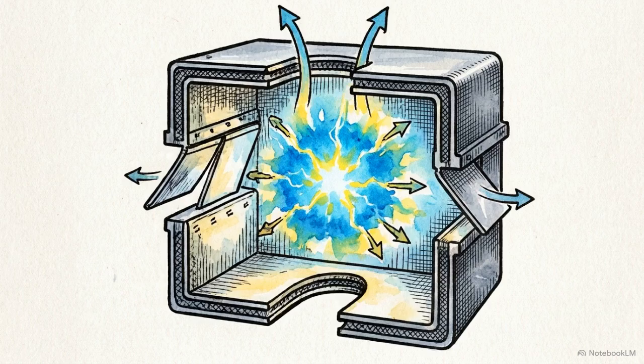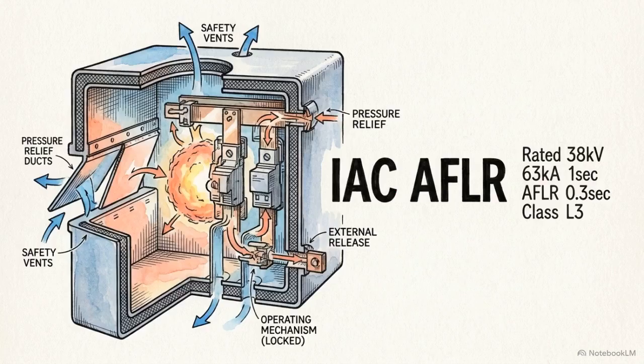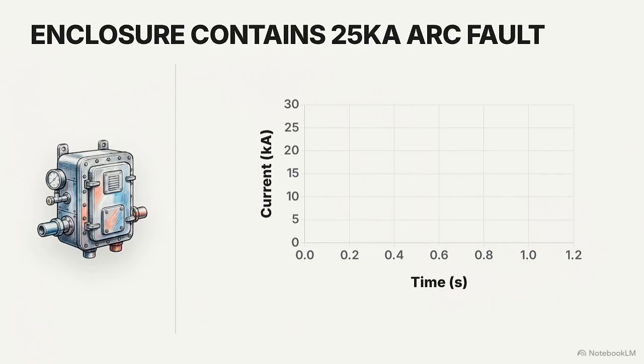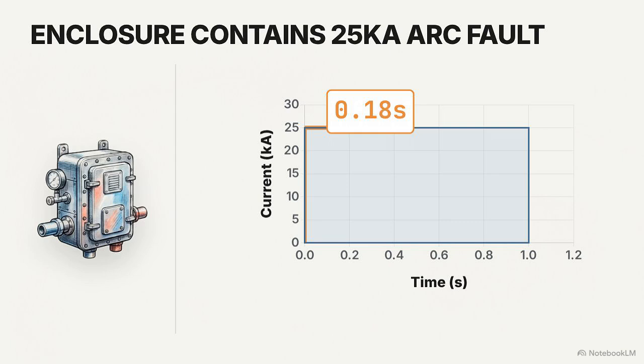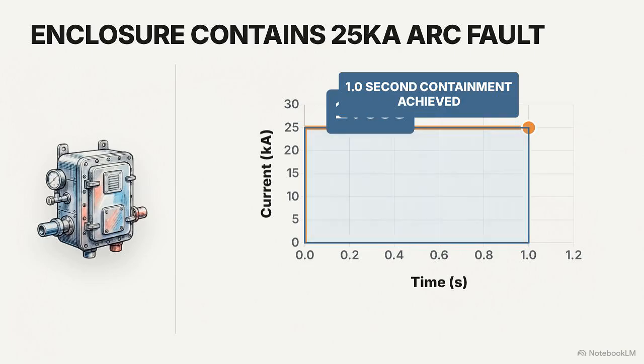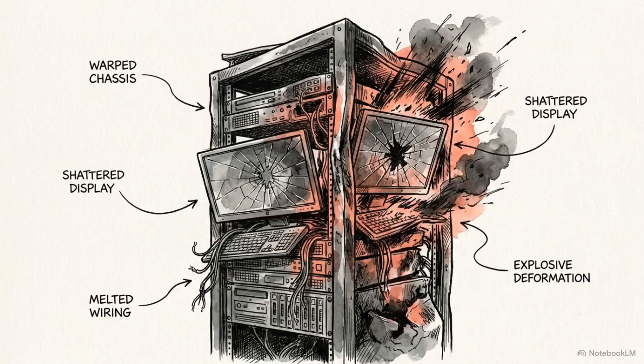If a component fails inside this sealed unit, the resulting arc flash generates immense pressure and heat. Therefore, the enclosure is built to meet a specific protection parameter, the Internal Arc Classification, or IAC-AFLR standard. A rating of 25 kiloamps for 1 second means the physical shell is engineered to contain a massive 25,000 amp internal fault for 1 full second. This provides the exact window of time required for the protection relays to trip and isolate the fault without the unit rupturing. Without this fault-tolerant physical shell containing the blast, any sophisticated electrical stabilization software running the grid is left completely vulnerable to catastrophic hardware destruction.